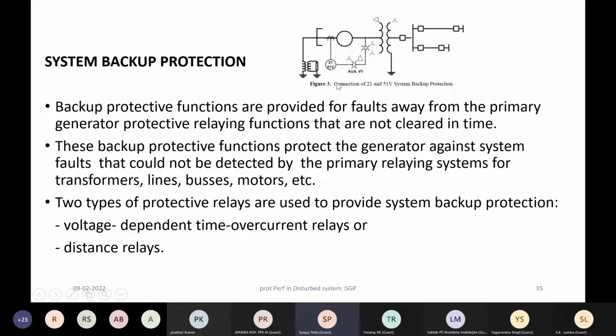Second is this impedance relay, which is acting as backup. This impedance relay has two stages. On one stage, it takes care of the phase-to-phase fault in the generator or the bus duct right up to the transformer. Typically in hydropower plants, you will have the generator transformer located at quite a distance from the generator. So this distance is sufficiently long, and this backup protection covers the generator as well as this interconnection right up to the generator transformer in its zone 1.